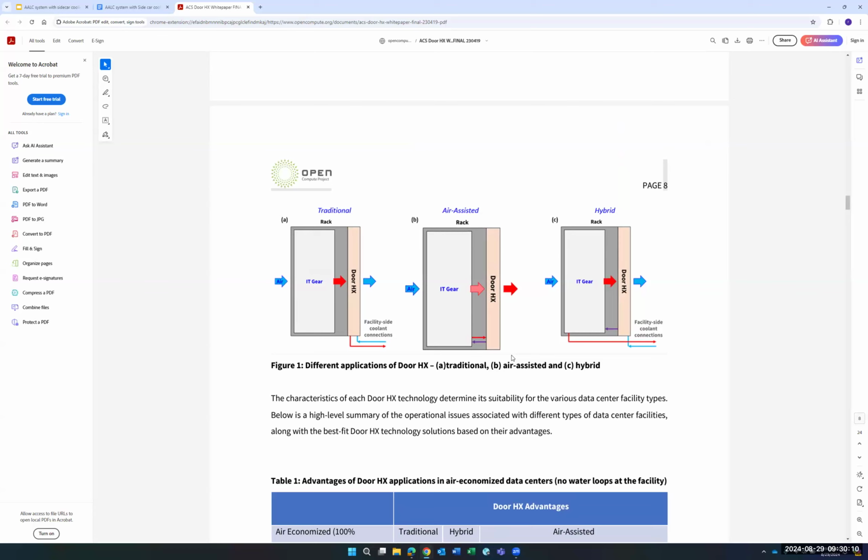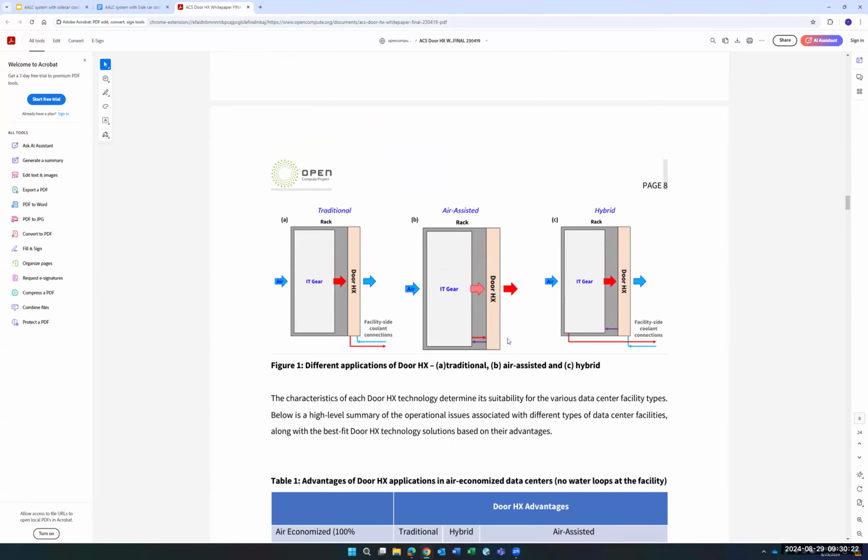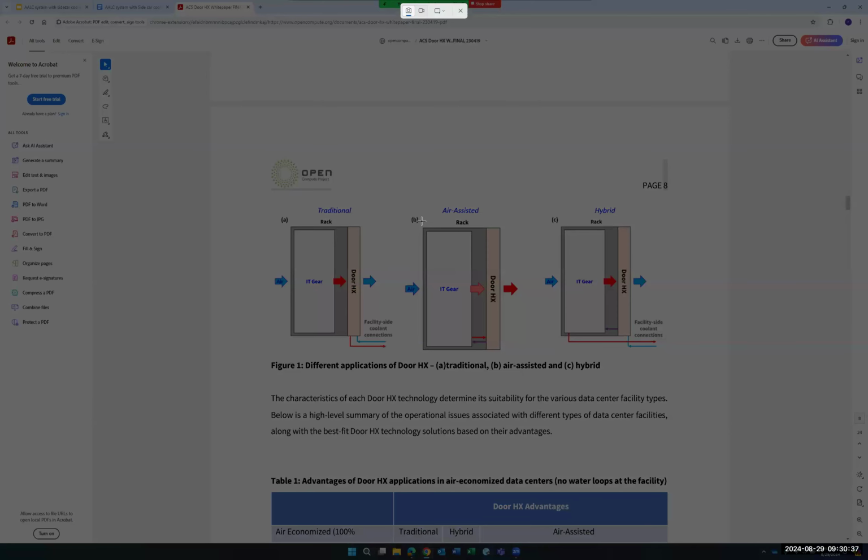But you could do the same kind of picture that you've got for the sidecar, but move the sidecar around behind it to show it like a rear door heat exchanger, and then put the same approach temperature for comparison that you would have for the sidecar, and then put what the upper bounds are for the cooling. So somebody could look at this in your presentation and say, okay, for a given approach temperature, I'm limited to so many kilowatts for a rear door.